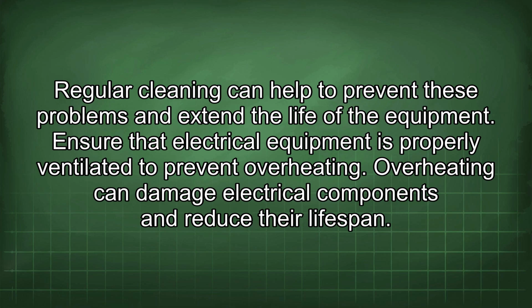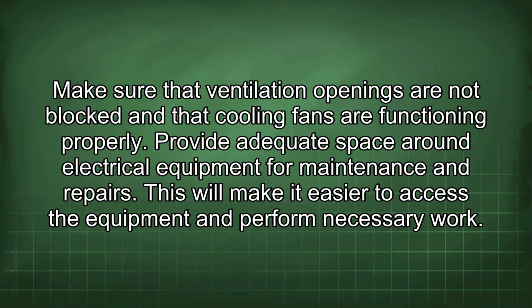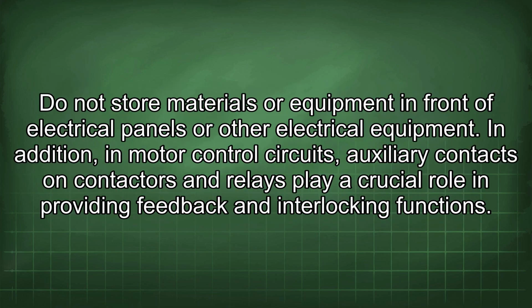Ensure that electrical equipment is properly ventilated to prevent overheating. Overheating can damage electrical components and reduce their lifespan. Make sure that ventilation openings are not blocked and that cooling fans are functioning properly. Provide adequate space around electrical equipment for maintenance and repairs. This will make it easier to access the equipment and perform necessary work. Do not store materials or equipment in front of electrical panels or other electrical equipment.